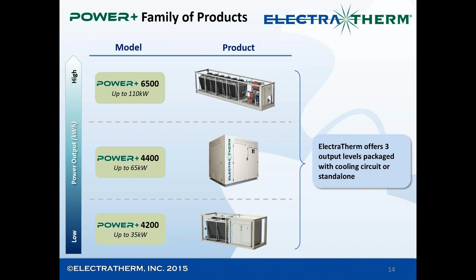On the fully integrated system, the type of construction we did at the Hess oil site, the integrated cooling circuit is supplied, and the hot water in and hot water out is the only mechanical connection - so the boiler feed and return, plus an electrical interconnect. We literally had two shipping containers set up in about two days, with an easy one to two day commissioning.